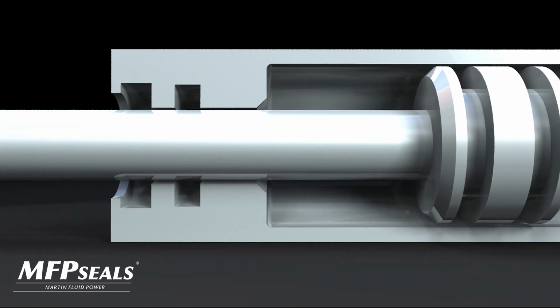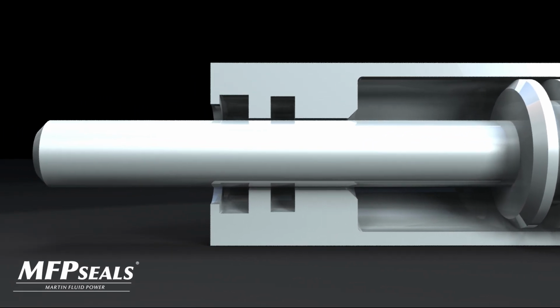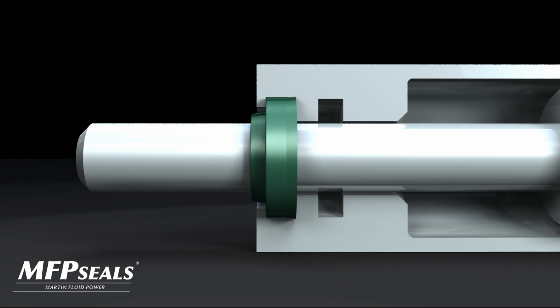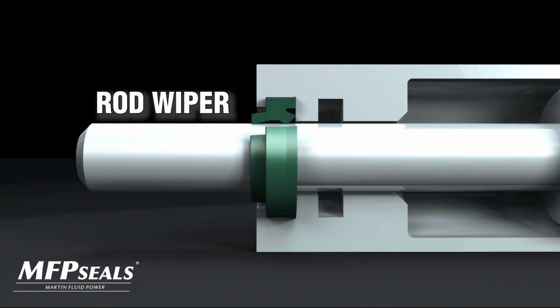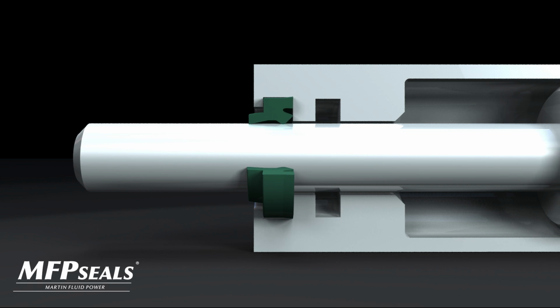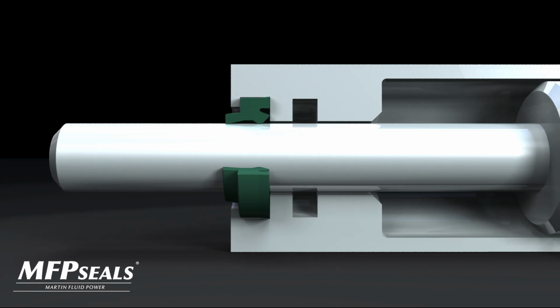Typically on a pneumatic linear actuator, the first seal in the gland, the one that is partially exposed to the environment, is a rod wiper, in this example, an H-wiper. The rod wiper is designed to keep contaminants out by wiping the rod clean as it extends and retracts. It also helps keep the air contained within the cylinder.